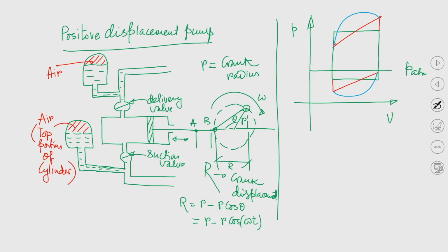Okay. So, you can understand that the curve drawn using the blue line is nothing but the effect due to fluid friction, which follows the Darcy equation. Okay. And the curve drawn using the red color is the modification due to the inertia effect. So, you can understand at the beginning of the suction stroke, pressure falls further.